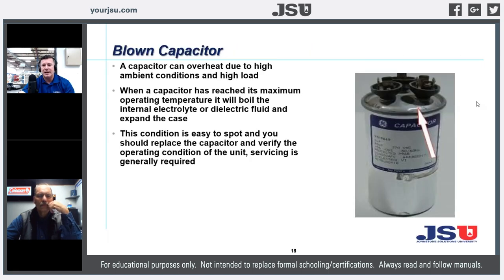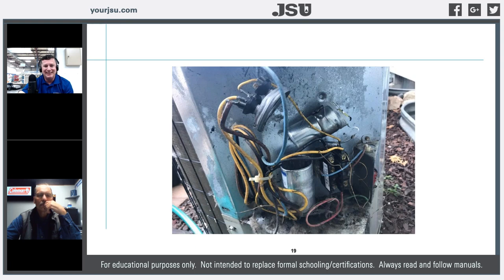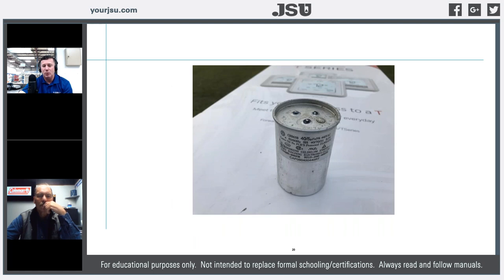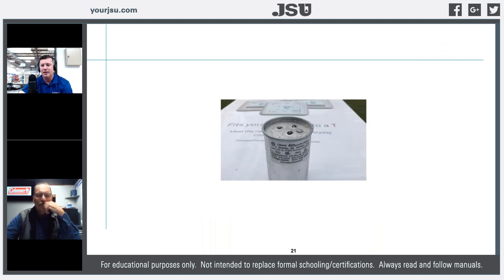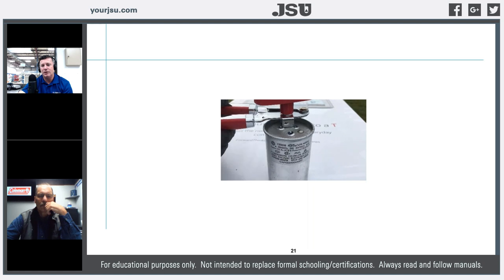We've all seen capacitors in the field that have been subjected to high current and high heat — they're pretty physically destroyed once they get to that point, all because they've been overworked. We were curious about the inner workings, so we cut open a capacitor with a can opener to see what was inside. This was one that came back to me under warranty. As technicians, we've never really talked about what is inside a capacitor or how it's constructed.